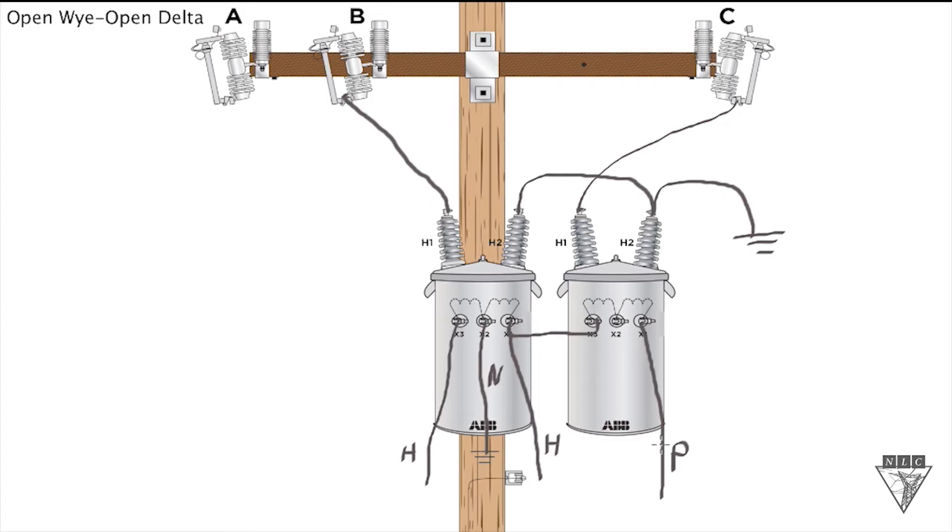You do not want to run the power leg to the home because then you'll be sending too much voltage into the home and you could burn up the electronics like TVs, computers, things of that sort. So you want to make sure that you identify what your power leg is and only use the power leg for the three phase load. For the single phase load, you want to utilize your two hot legs and the neutral.